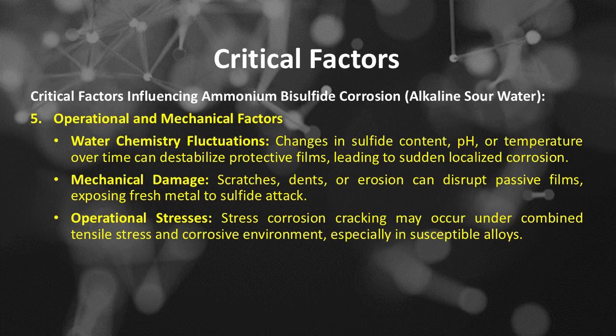The second is mechanical damage. Scratches, dents, or erosion can disrupt passive films, exposing fresh metal to sulfide attack. The third is operational stresses. Stress corrosion cracking may occur under combined tensile stress and corrosive environment, especially in susceptible alloys.